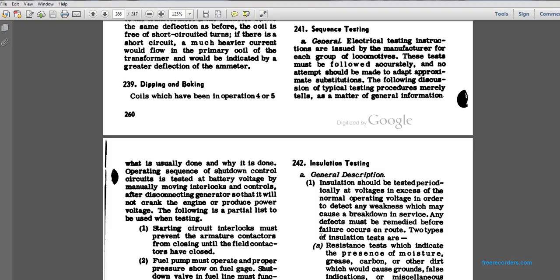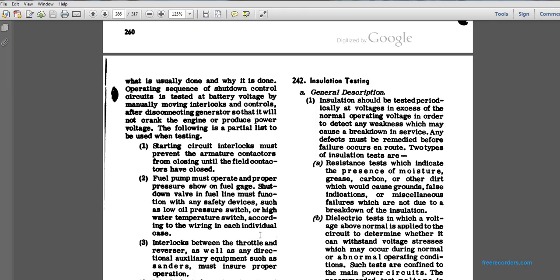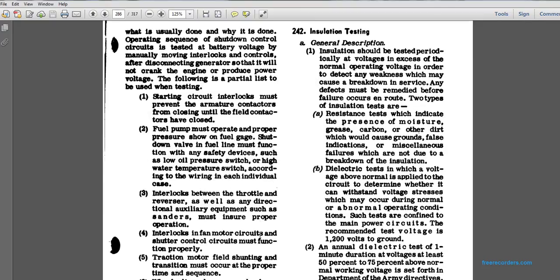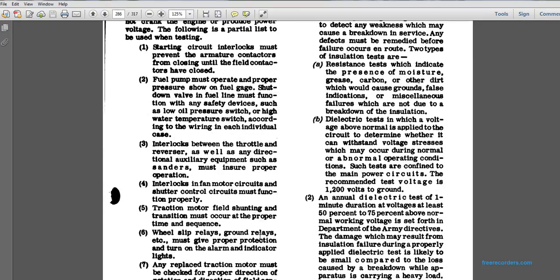Operating sequence and shutdown control circuits is tested at battery voltage, manually moving interlocks and controls after disconnecting the generators so that it will not crank the engine. The following is a partial listing of items that may be used in testing. 1. Starting circuit interlocks prevent the armature contactors from closing until the field contactors have closed.